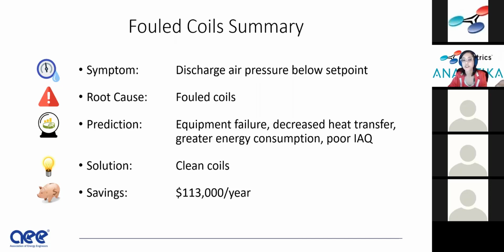I used to kind of gloss over that in all these presentations. It's funny now, right? That's huge. Indoor air quality, fouled coils, and what can get stuck to those coils, and how are you going to get that stuff off those coils often enough? And so analytics can really help you look at that. Symptom, discharge air pressure below set point. Not just below set point, we can see how much below, how long has it been below set point? What was it doing 2 years ago? Was it this below set point? We really can get better information to the customer to help reduce that implementation period and make sure that that issue is solved quickly. The root cause here were fouled coils.